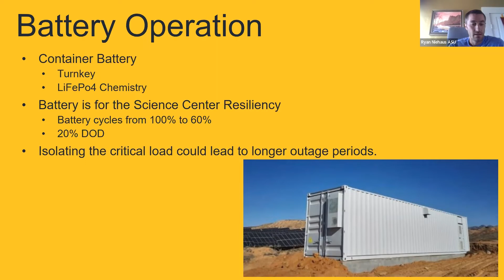The container battery was chosen for a turnkey solution. The container comes with all the systems needed to operate the battery safely. The lithium iron phosphate chemistry is capable of deep cycling, is environmentally friendly, and is very stable, making it ideal for storage solutions. The battery is designed to support the science center for a 1 hour outage during peak usage, starting at 60% capacity. If the critical load in the science center could be isolated or reduced, longer outage periods or maybe islanding are possible, but more information is needed to make this decision. The battery is cycled from 100% to 60% for battery health. A battery size for peak shaving has negative economic value at this time.